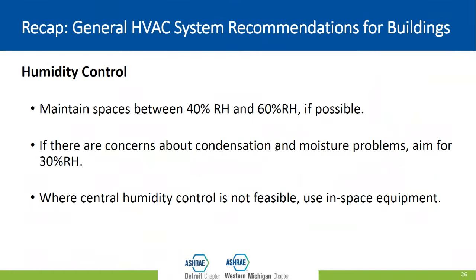And if you currently don't have central humidity equipment in your facility, right, it's not at your air handler, it's not in your mechanical room, then consider using in-space equipment. That can either be portable equipment or it could be wall-mounted equipment where you're bringing the humidity right to the space where the people are. You want to make sure, though, that for any remote equipment that you have that's in the space, that's not in your central mechanical room, your facility staff is aware of it, they know that it's there, and that they know it needs to be maintained.